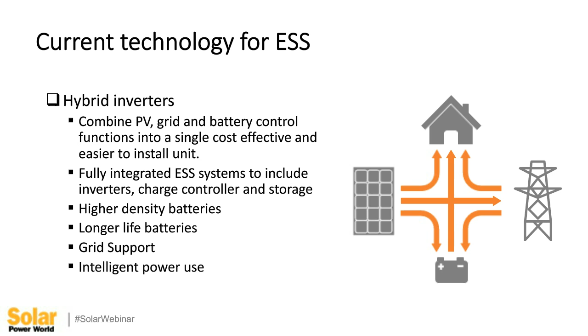So let's look at the components of a new ESS. We've got the hybrid inverter. So if you look at this, you've got your PV coming in. That comes into the inverter, satisfying the needs for the battery, satisfying the needs for the grid, and your load. You've got the battery coming in. So again, going through the inverter from the battery to the grid to your load, whatever it is that your particular system needs at that time.